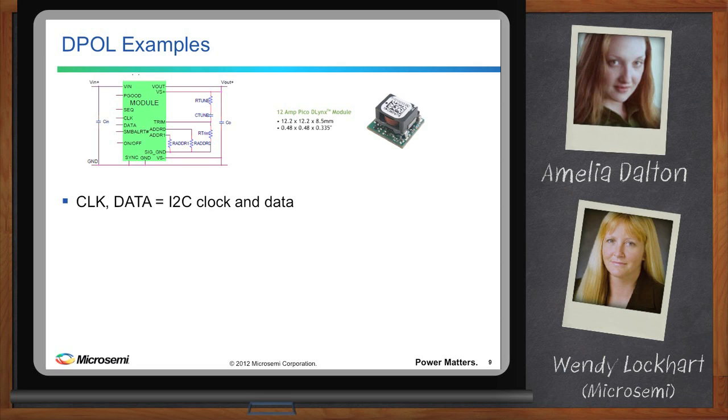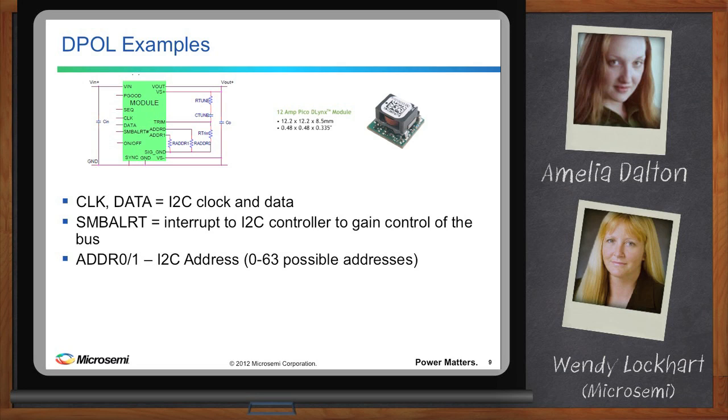To start with, communication leverages the power management bus, or PM bus, through an I2C connection, which is used for initialization or monitoring. Okay. The addressing identifies the device to the controller, and then by adjusting the external resistor values, the address of the device on the bus is set. This device has up to 64 possible address combinations, which indicates the number of devices suppliers are planning for to be able to support them on a single system.